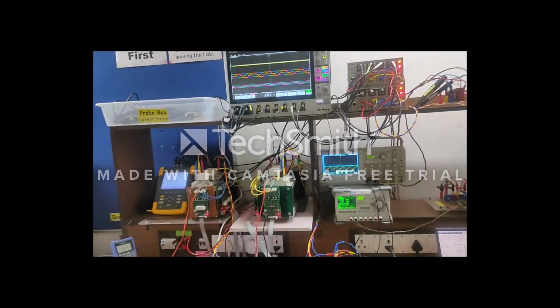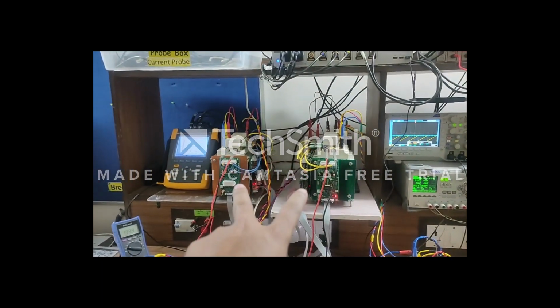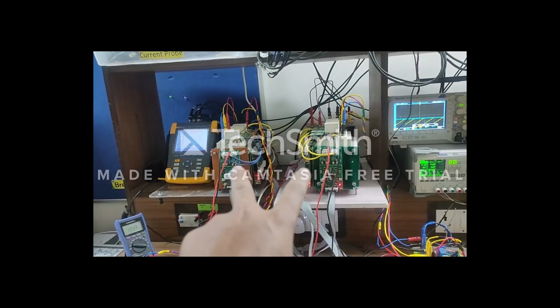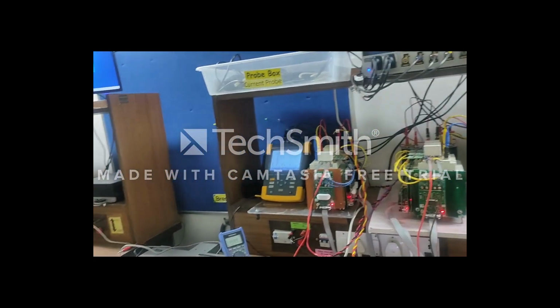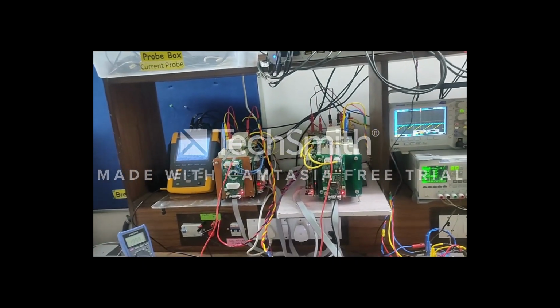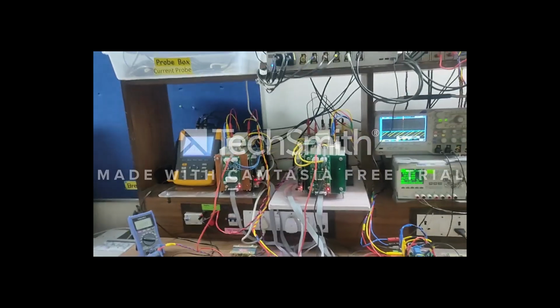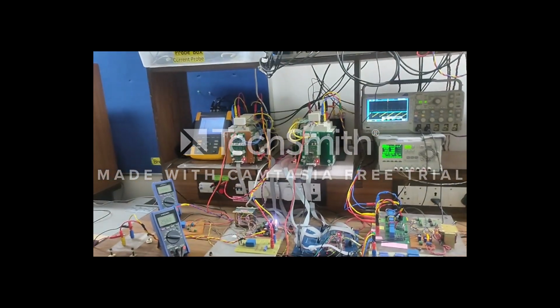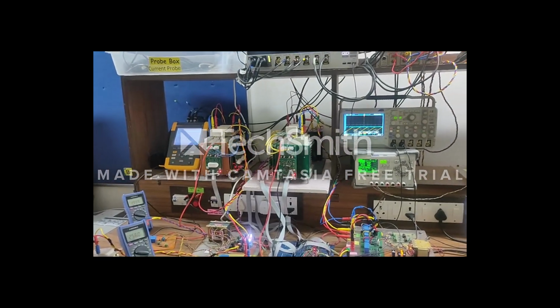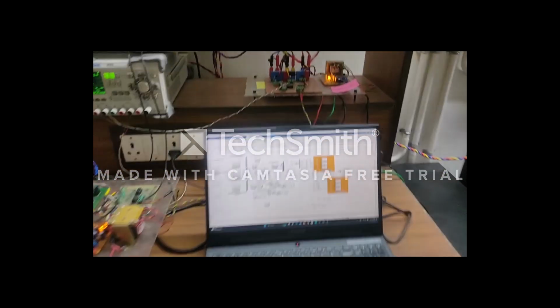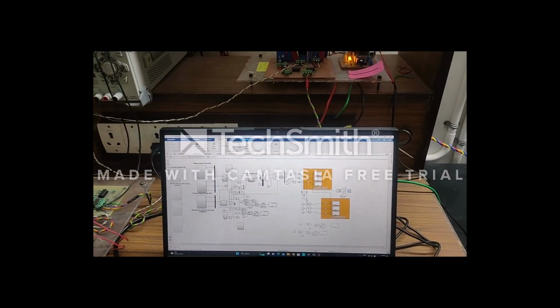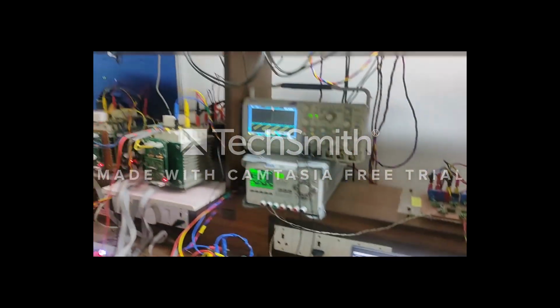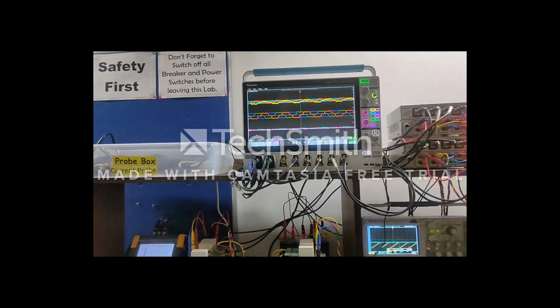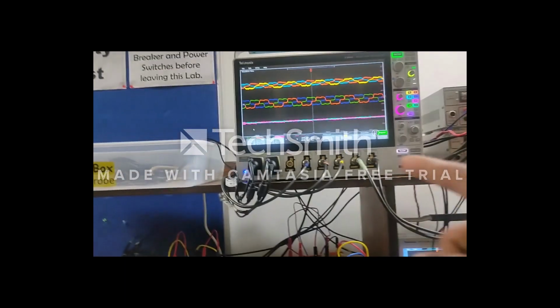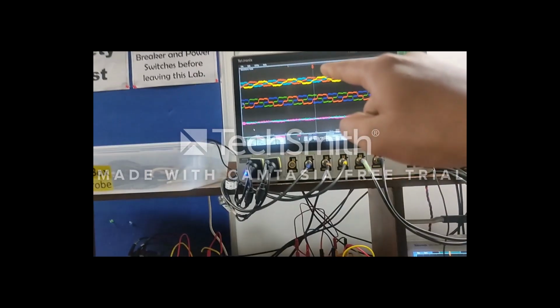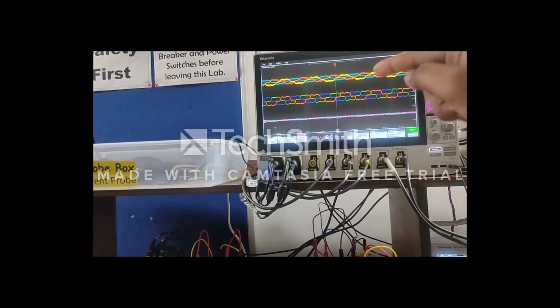In this mode 1 operation, the control logic of both inverters is given the same reference, and this reference is generated by the solar emulator maximum power point current reference. Both inverters are controlled by the same reference, and both inject the same power. If we turn on the pulses to the inverters, we start compensating the harmonics from the grid. Here the available power of the sources is the same as the load power, so the injected grid current is 0, and the total power coming from the sources is given to the load.